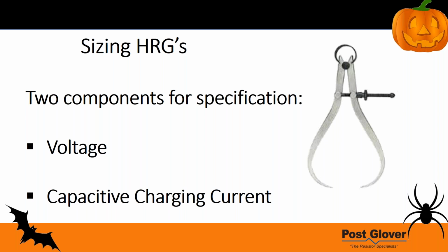I don't really care how big your generator is—if it's a 10 MVA generator, it doesn't really matter, except that for a 10 MVA system you're probably going to have a much larger system, more wire, more loads. So I do care about how much wire there is and how much motor load you have, because it impacts the capacitive charging current. But these are the things you want to worry about.